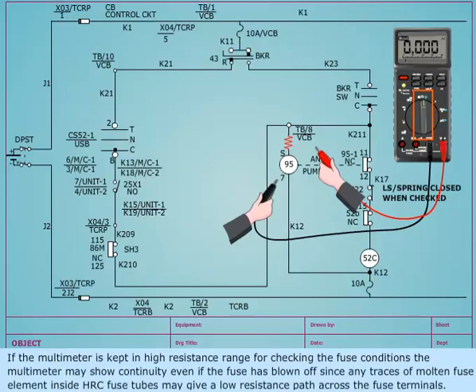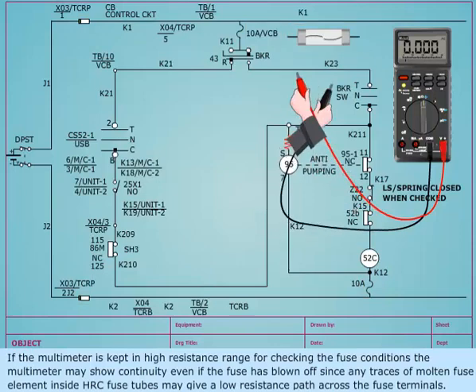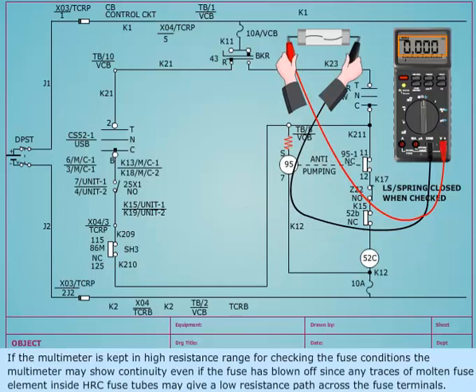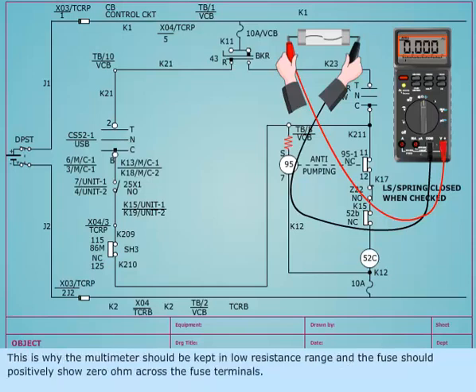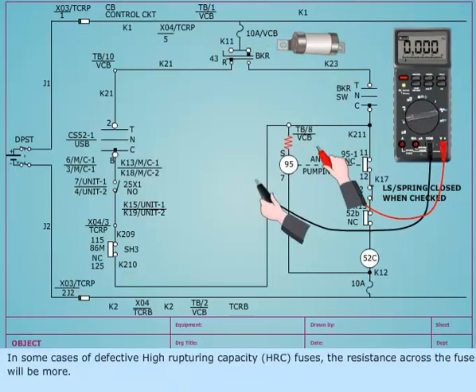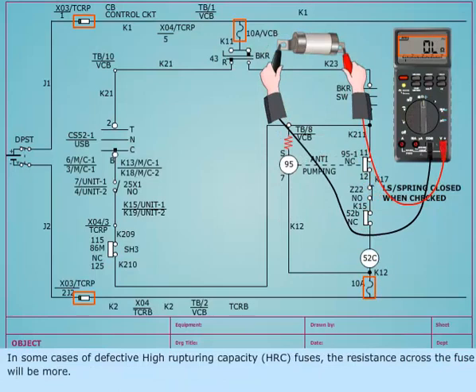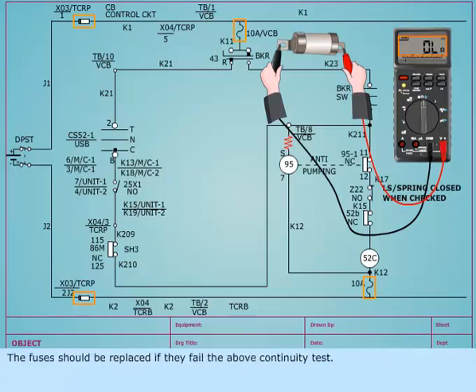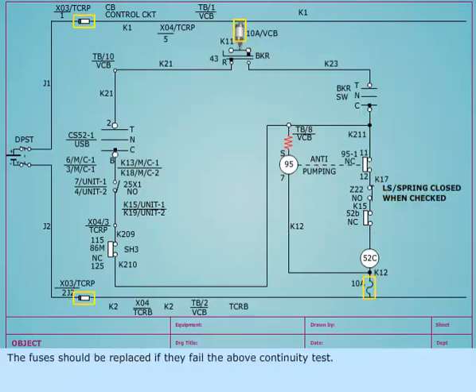If the multimeter is kept in high resistance range for checking the fuse conditions, the multimeter may show continuity even if the fuse has blown off, since any traces of molten fuse element inside HRC fuse tubes may give a low resistance path across the fuse terminals. This is why the multimeter should be kept in low resistance range and the fuse should positively show 0 ohms across the fuse terminals. In some cases of defective high rupturing capacity HRC fuses, the resistance across the fuse will be more. The fuses should be replaced if they fail the above continuity test.